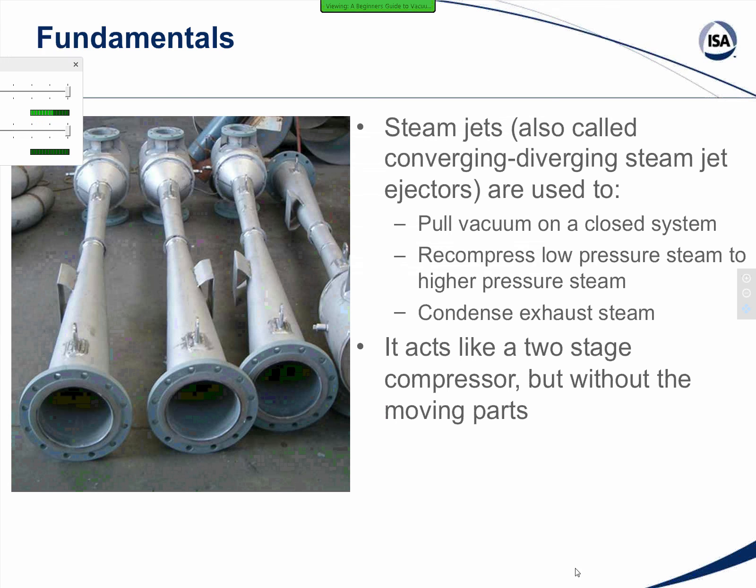If you haven't seen one before, here's a picture of a few steam jet ejectors. These are commonly used to pull vacuum on a closed system, like batch reactors that I have here on site. In addition, they can be used to recompress steam to higher pressures or even to condense steam. If you're familiar with the concept of a compressor, the way that these work with the converging and diverging design acts as a two-stage compressor but without all the upkeep that you normally have with moving parts. This makes ejectors more reliable than a vacuum pump system, at least in terms of direct maintenance, but they have plenty of system complications that we'll be talking about over the next few slides.